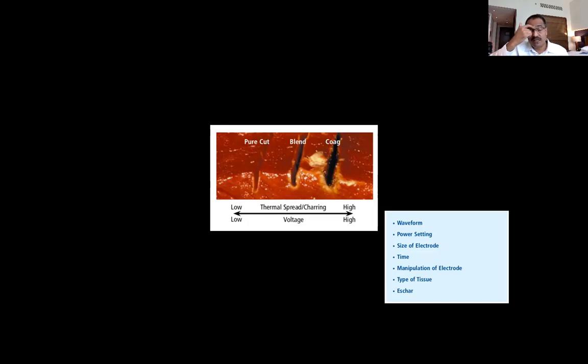That I will come to when I show you the videos of how to make effective use of electrosurgery in your day-to-day surgeries. It would depend upon what waveform you are using. Like I said, better to use a cutting current. Power settings, how much voltage you want, okay? The size of the electrode, because if you have a very thin electrode, the concentration, the density of the current depends upon the size of the electrode, I mean the instrument.